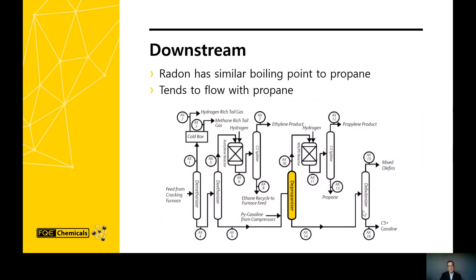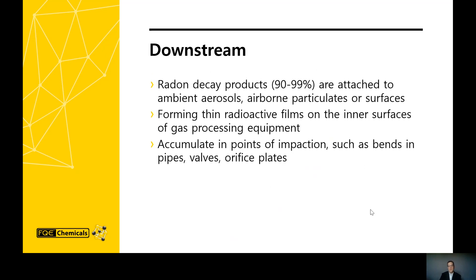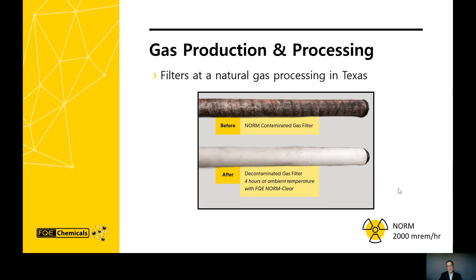Downstream, in a typical fractionation train for natural gas as shown here, because radon preferentially travels with the natural gas and has a similar boiling point to propane, a disproportionately high percentage of radon can concentrate in the propane streams and, to a lesser extent, the ethane stream. Also downstream, a majority of the radon decay products attach themselves to ambient aerosols or particles, thus forming a thin film or layer on the inner surfaces. Therefore, they begin to accumulate at points of impaction, such as bends with elbows in the pipe and orifice plates.